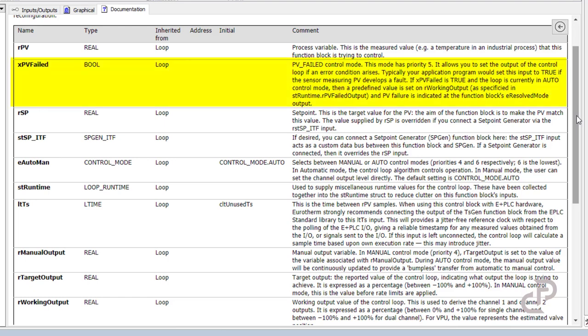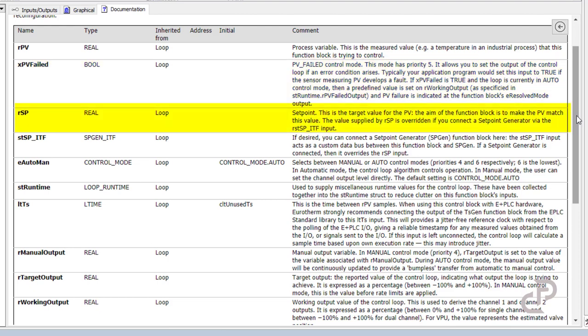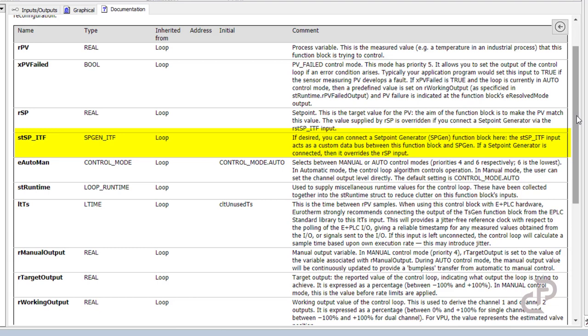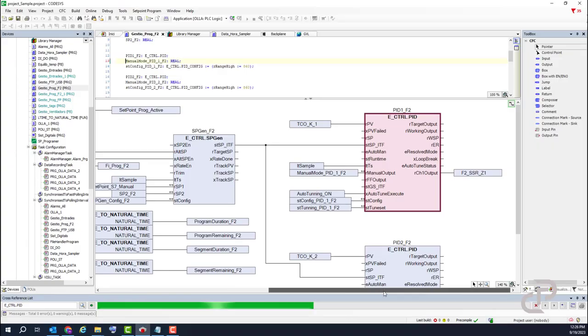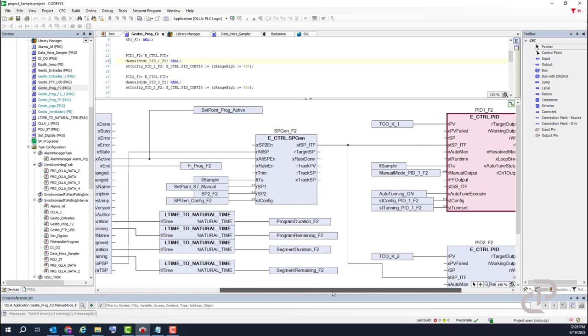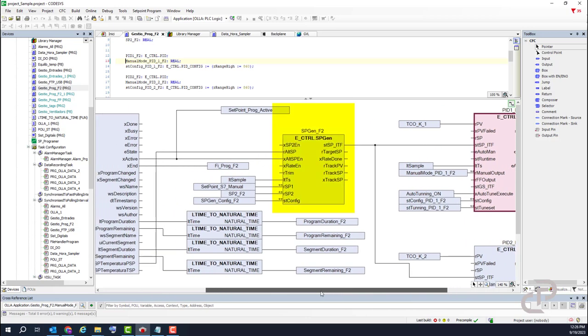xpv_failed can be used if there is any fault in sensor measuring. rsp is the setpoint and target value for the process value. stspitf is used if you connect the setpoint generator function block. If a setpoint generator is connected, then it overwrites the rsp input.